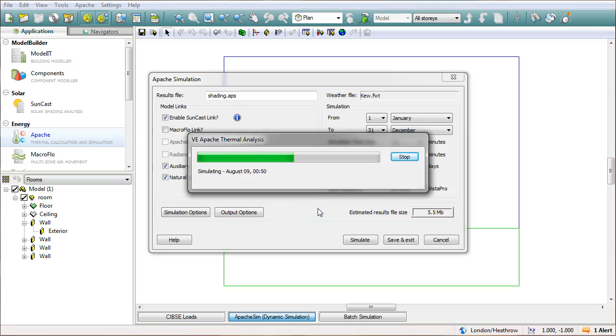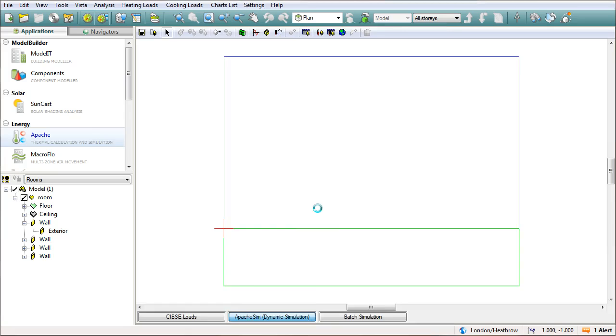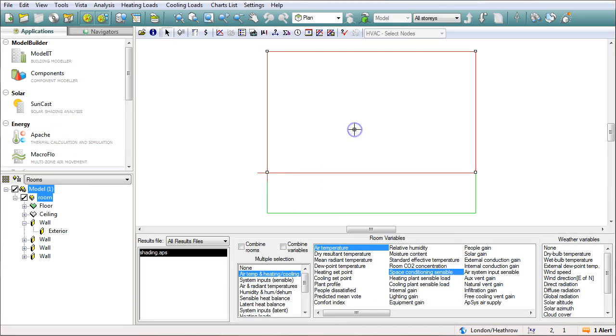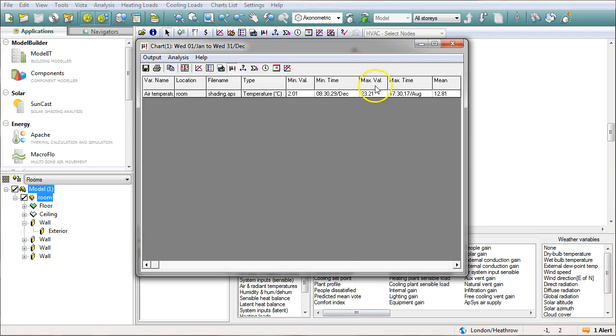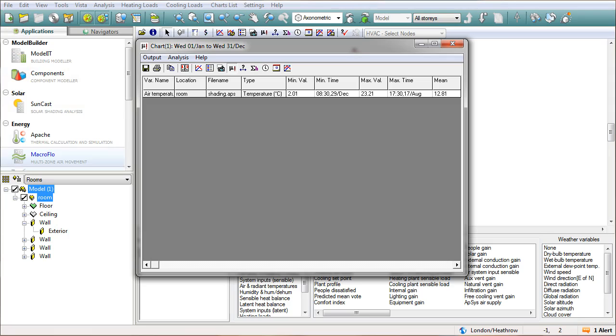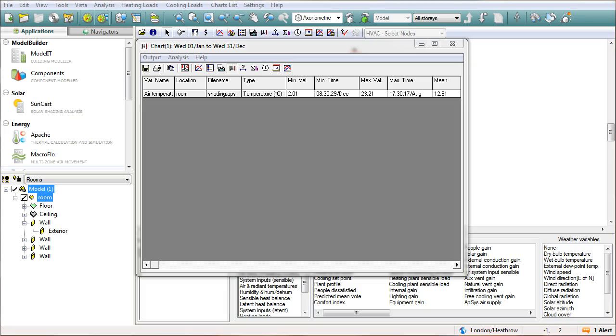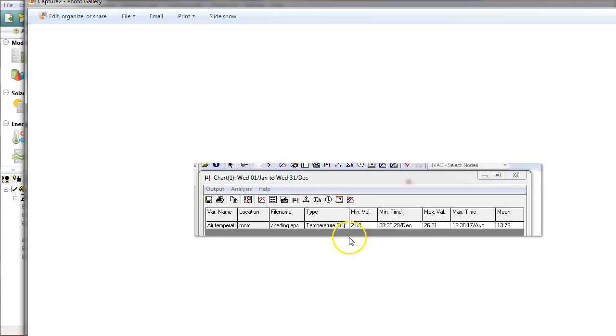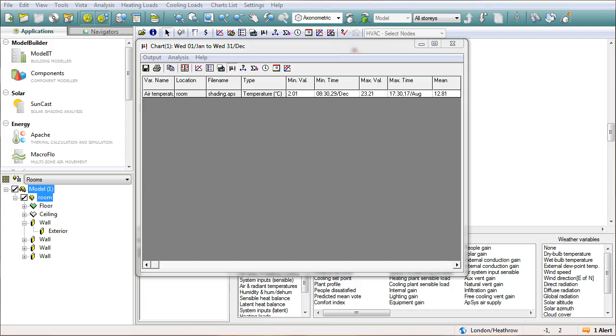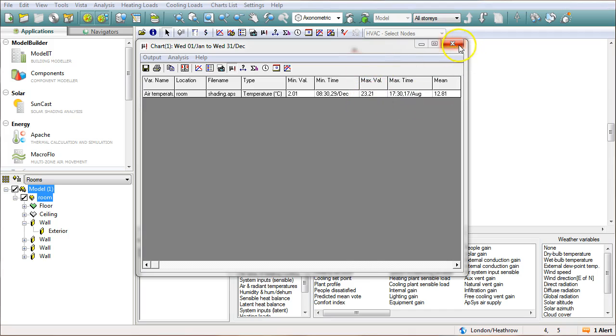And what I'm going to look for here is I'm going to look for my air temperatures to see have they been affected by the presence of the canopy. So air temperature synopsis. So look at my air temperature maximum now. It's been brought down to 23 degrees. If I just show you the capture, the screen capture that I had from earlier that maximum air temperature in there was 26. Okay so we've gone from just over 26 degrees down to just over 23. The only thing that's been changed is we've put a canopy on there so effectively that's shading, it's stopping the sun from warming the room up too much.